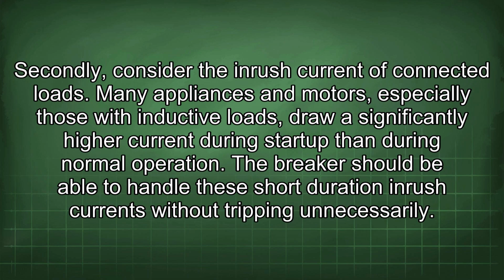Secondly, consider the inrush current of connected loads. Many appliances and motors, especially those with inductive loads, draw a significantly higher current during startup than during normal operation. The breaker should be able to handle these short-duration inrush currents without tripping unnecessarily.